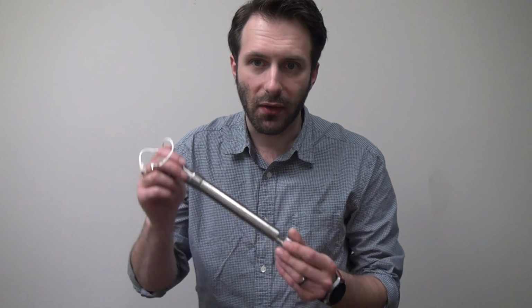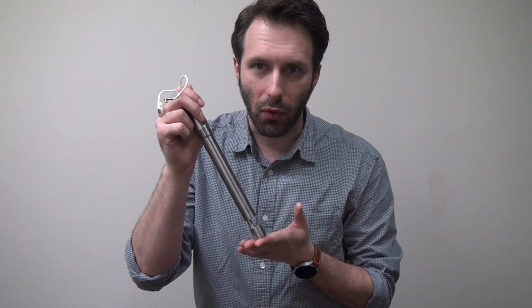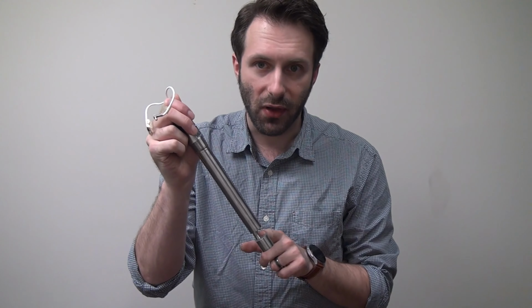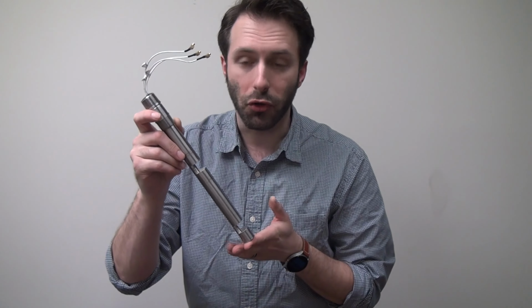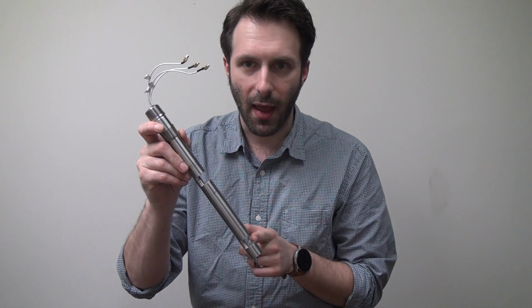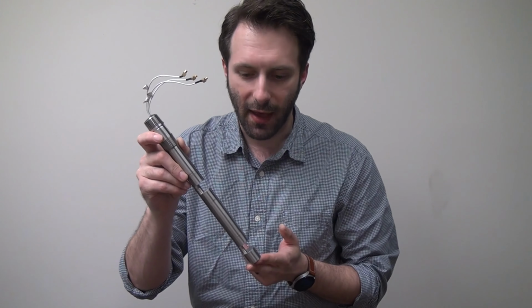The 371 is indicating that it is a single point probe as seen here, with this style being the N or notch type. Here I have a 372 or a dual point probe, also with the N or notch style of cavity. When ordered from the factory as a complete unit, the device will arrive already assembled. However, if you're ordering a replacement electronics or probe for an existing unit, those will need to be assembled in the field.